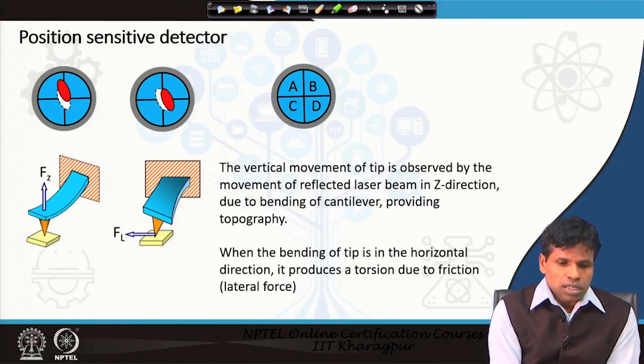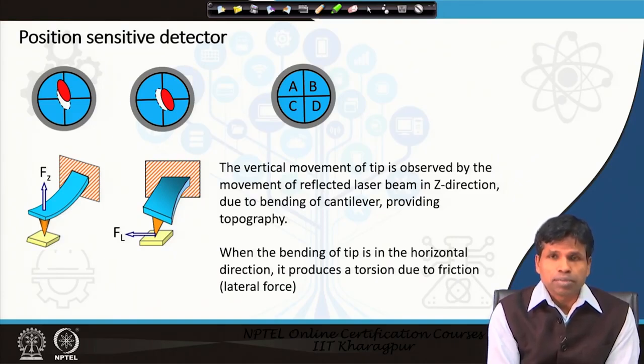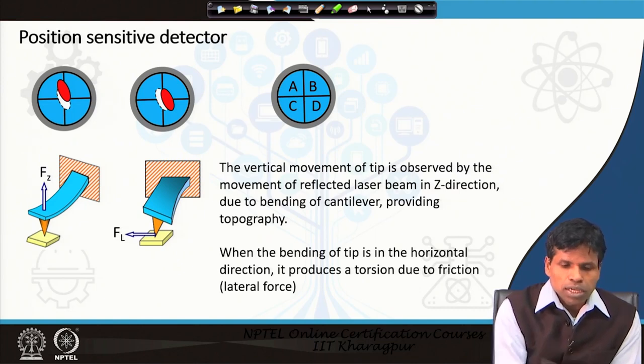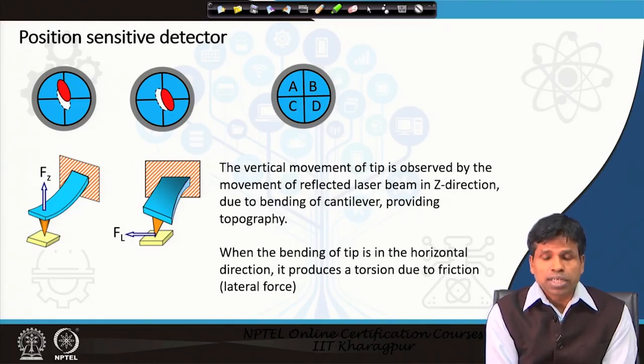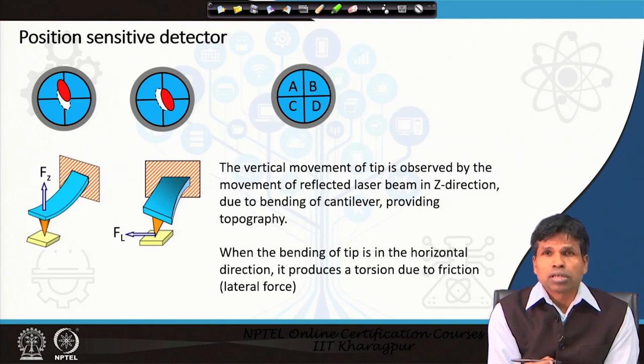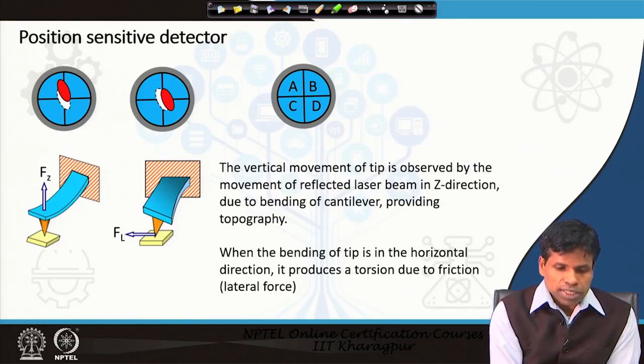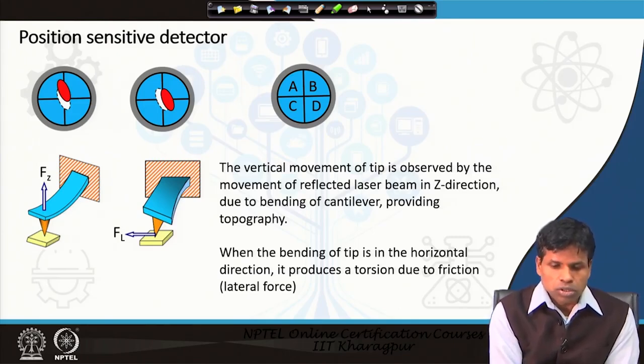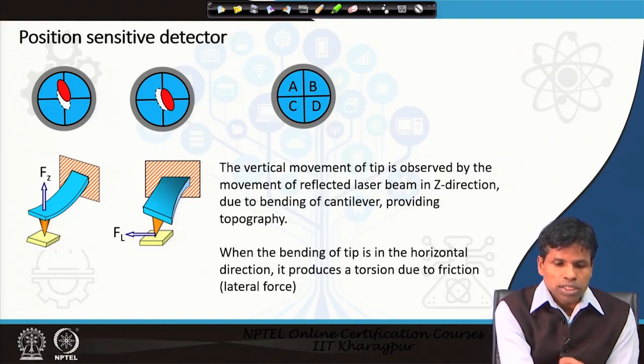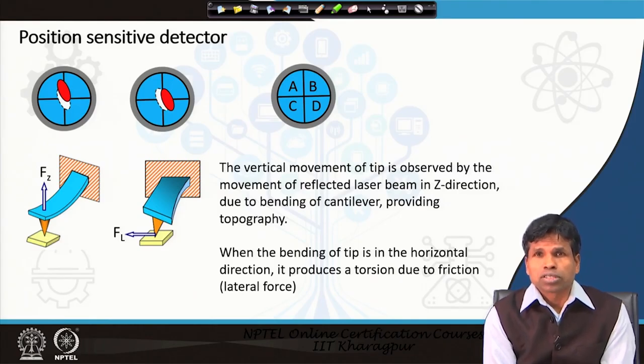As seen in the schematic, we have a position-sensitive detector on which the laser beam falls. In the vertical movement of the tip, the laser beam will move in the upward Z direction on the position-sensitive detector. We can measure how much the tip is deflected in the Z direction and thereby measure the distance between tip and sample. In other cases, if there is a bending of the tip causing horizontal movement, the reflected light on the position-sensitive detector will move in the horizontal direction.